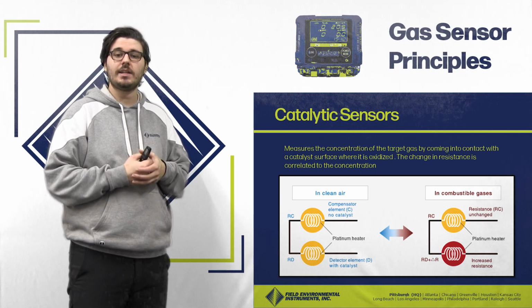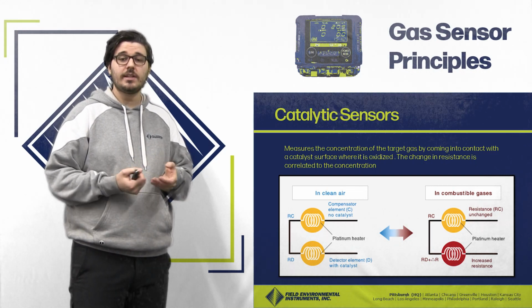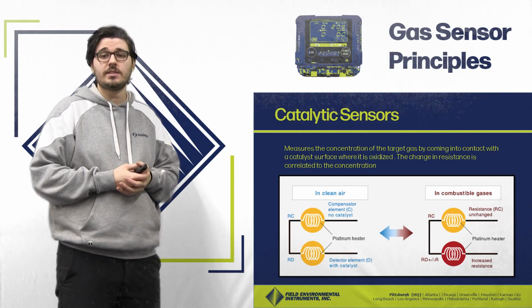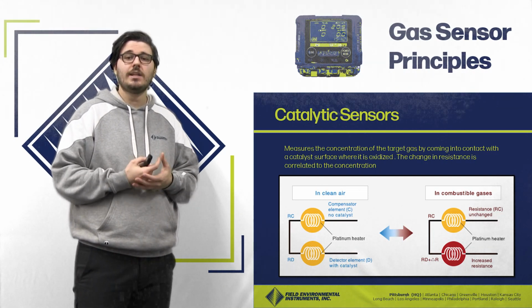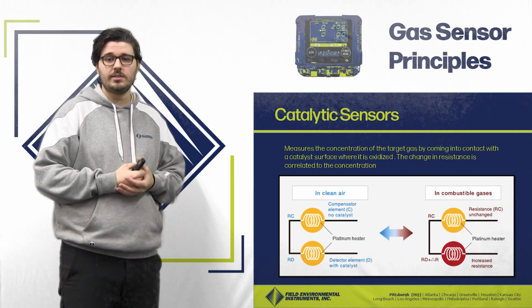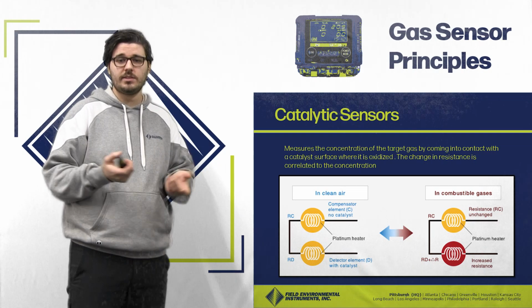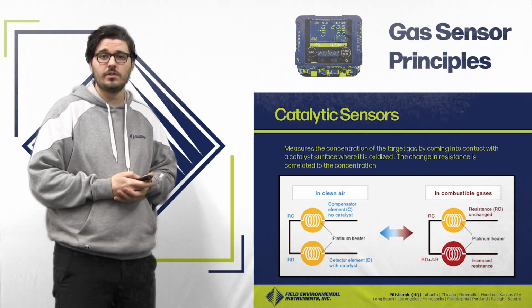Next up, we have catalytic sensors. So catalytic sensors are going to measure the concentration of gas by coming into contact with a catalyst surface where it's oxidized, and the change in resistance is going to be correlated to the concentration.